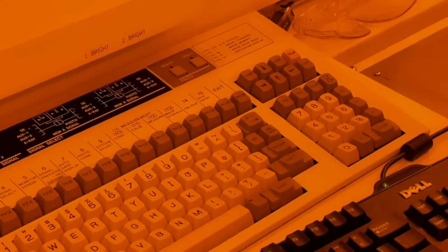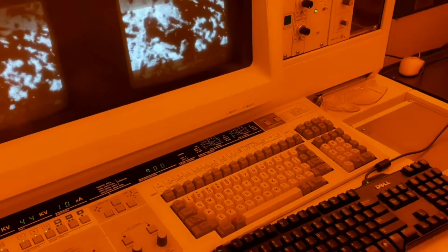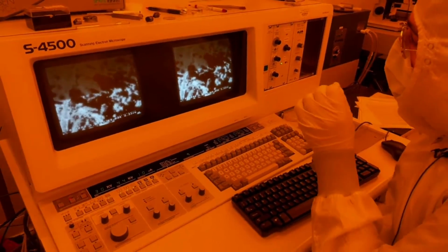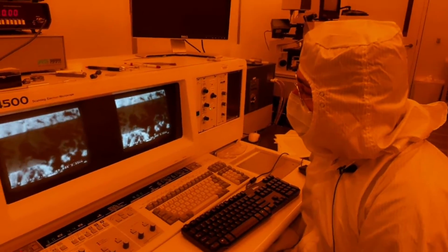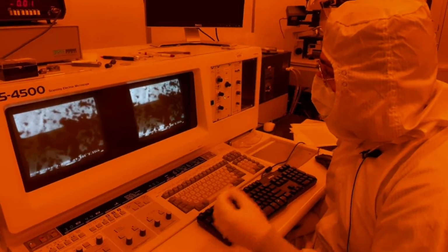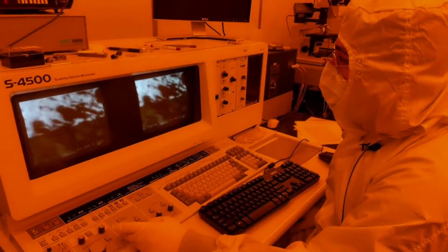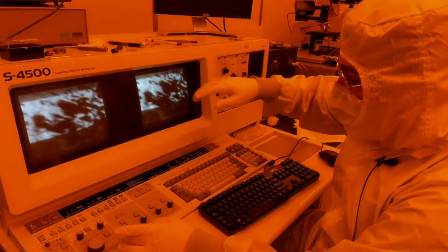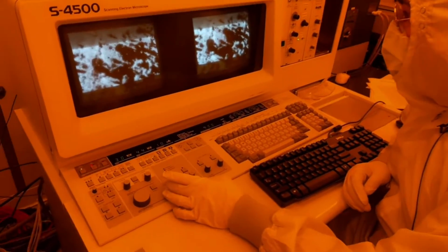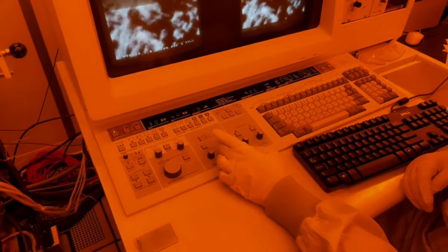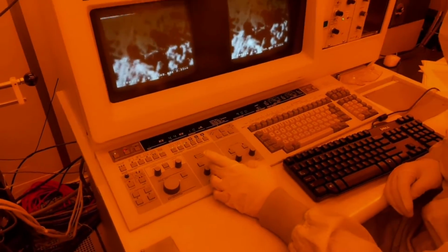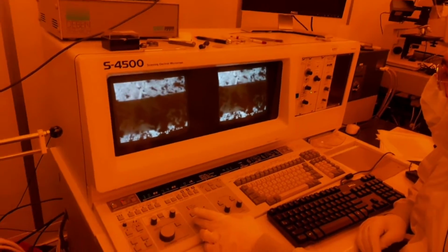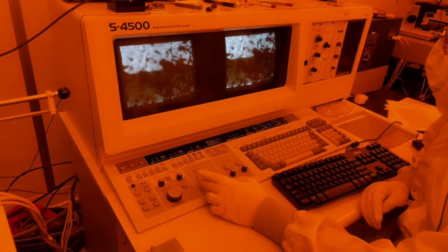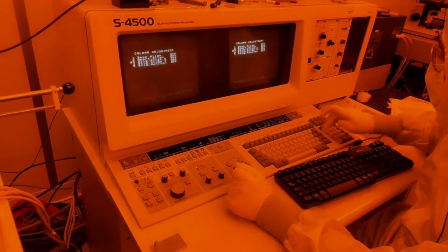So this is going to have to be at a higher magnification. And what this does is it wobbles the focus. If the aperture is aligned, the features should still stay in place, but they'll kind of go in and out of focus. If it's poorly aligned, you'll see it kind of moves back and forth. So you want to reduce that lateral and vertical motion as much as possible, although it's still going to wobble. That's a little bit better. That's pretty all right, so we'll just stop there.